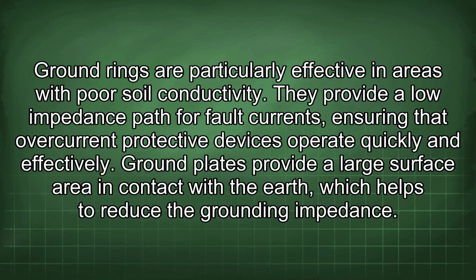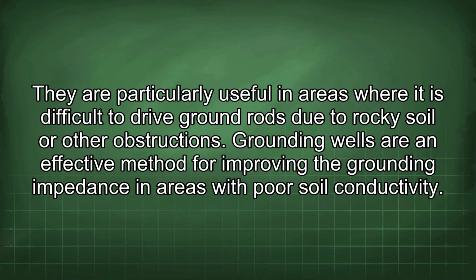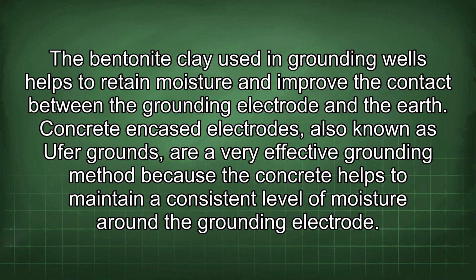Ground plates provide a large surface area in contact with the earth, which helps to reduce the grounding impedance. They are particularly useful in areas where it is difficult to drive ground rods due to rocky soil or other obstructions. Grounding wells are an effective method for improving the grounding impedance in areas with poor soil conductivity. The bentonite clay used in grounding wells helps to retain moisture and improve the contact between the grounding electrode and the earth.